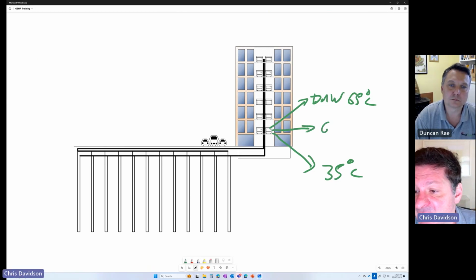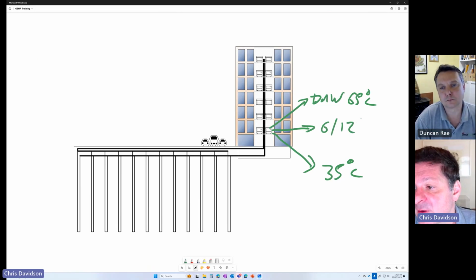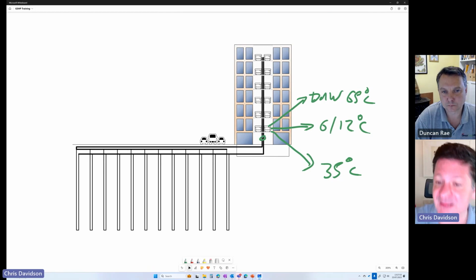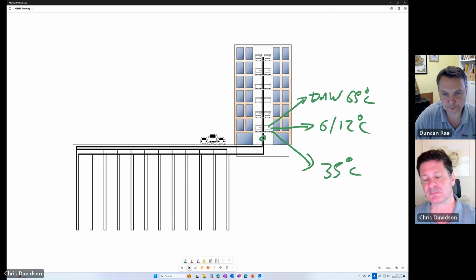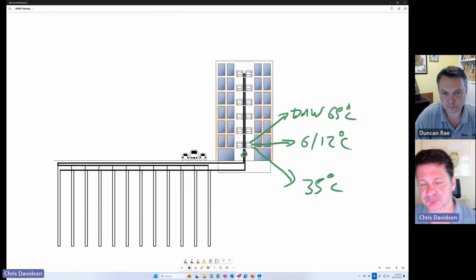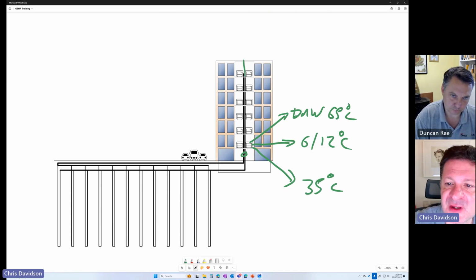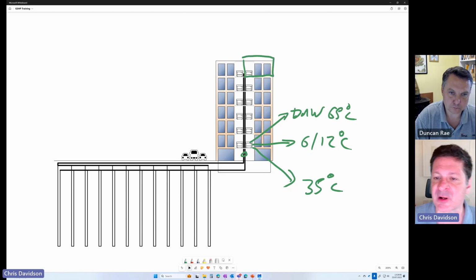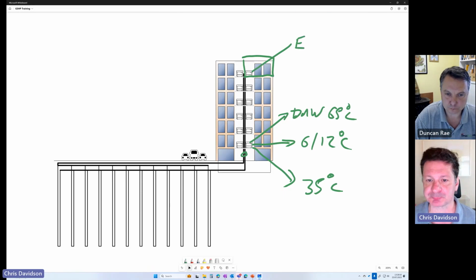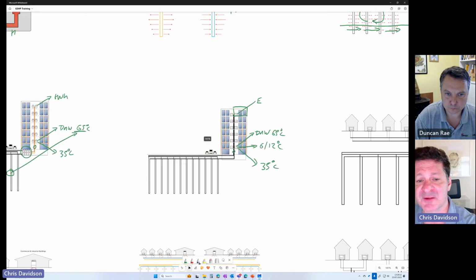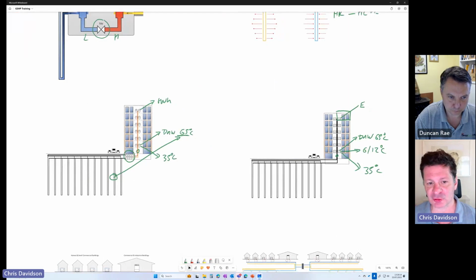So we could be providing, say, cooling at 6 degrees, 12 degrees return on that circuit. Or indeed, we can actually use that ground loop directly for cooling as well. So we're not now compromising our space heating efficiency in order to deliver our domestic hot water. One final point to make on this is that all of the run costs associated with that dwelling are associated with the electrical consumption of the heat pump. So we've got quite a different technical and commercial solution between the two options here.